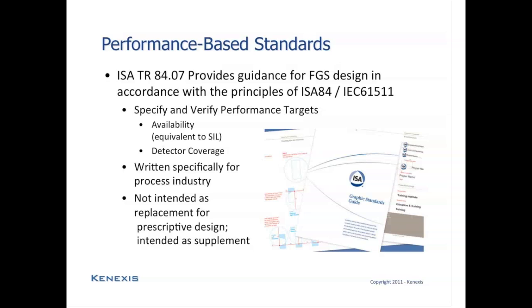In general, the way the IEC 61511 standard works is that performance targets are specified for each safety instrumented function or a control loop that performs a safety purpose. And that target is selected based on the risk associated with the hazard that the safety instrumented function is intended to prevent. Well, while this approach works very well for safety instrumented systems, it falls a little bit short for fire and gas detection and suppression systems because FGS systems in general do not prevent a hazard, they mitigate a hazard, making the consequence smaller instead of preventing it altogether. As a result of that subtlety of the difference between preventive and mitigative systems, a lot of additional engineering and a lot of additional specification needs to be performed in order to fill the gaps.